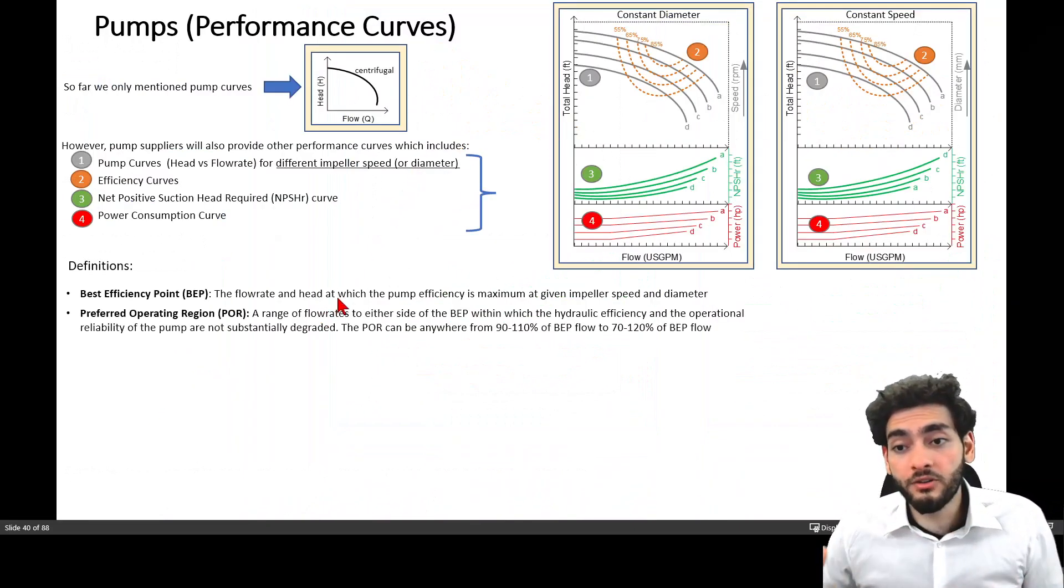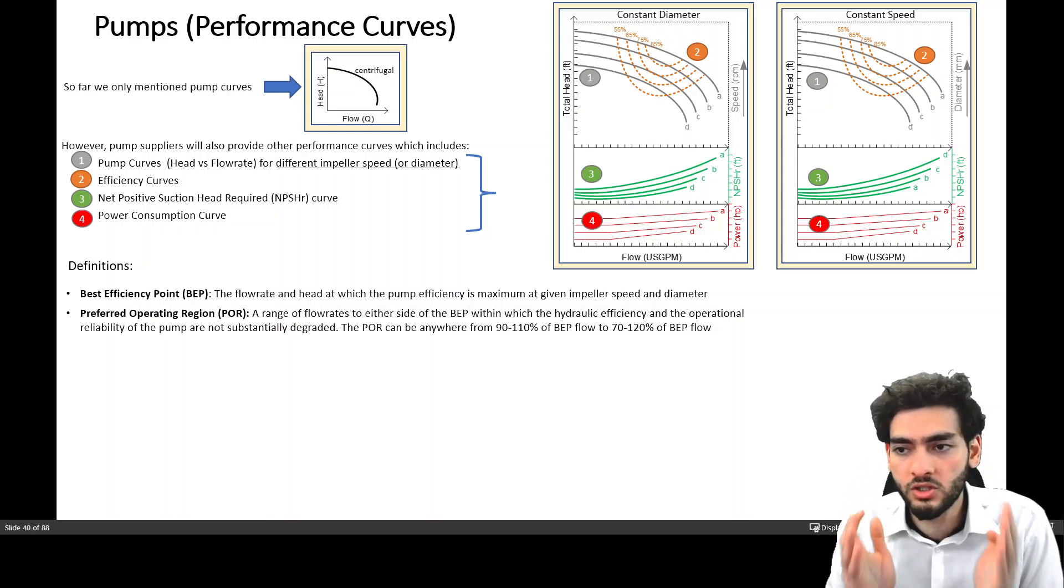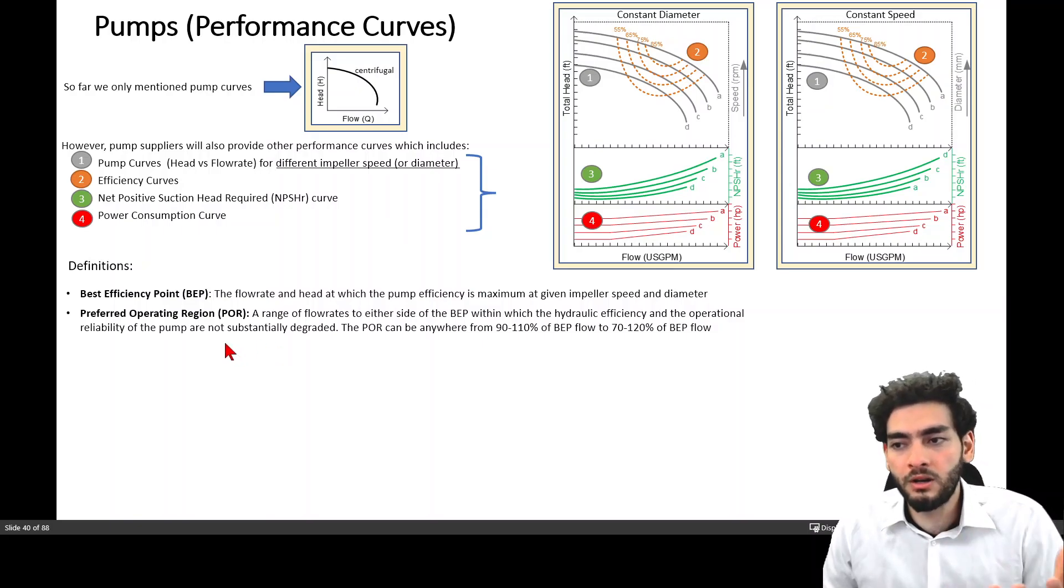The preferred operating region is a range of flow rates to either side of the best efficiency point within which the hydraulic efficiency and the operational reliability of the pump are not substantially degraded. And the preferred operating region can be anywhere from 90% to 110% of the best efficiency point and the flow to be between 70% to 120% of the best efficiency point flow.